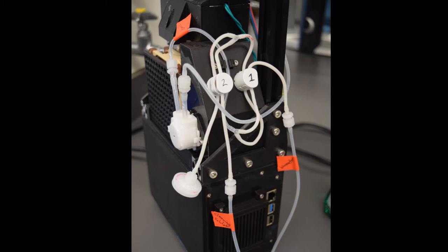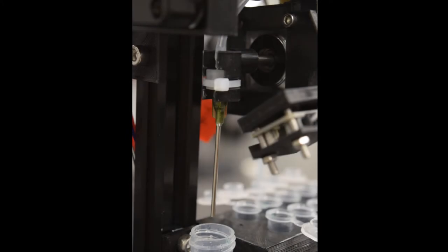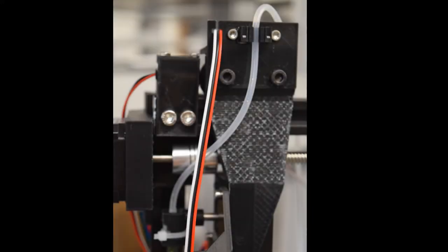From the right side of the peristaltic pump, another approximately 70 millimeter section of tubing is connected with a male luer lock barb, which then feeds around the back of the instrument to another male luer lock barb with a blunt 18 gauge needle. This luer lock and needle is inserted into the needle holder, and a zip tie is used to hold this in place in the needle holder. This tubing is also inserted into the fluid sensor on the gantry. All tubing except the tubing that's actually in the peristaltic pump is 1/8-inch outer diameter tubing.